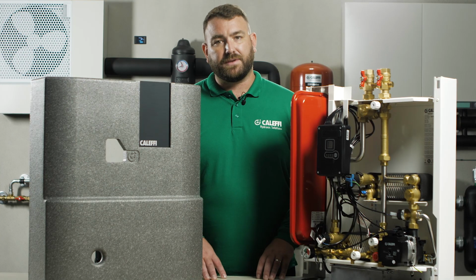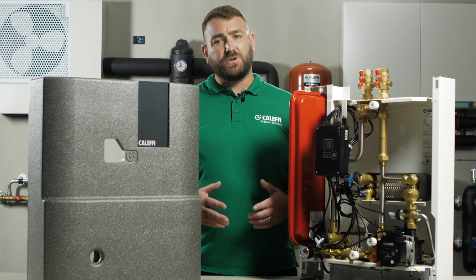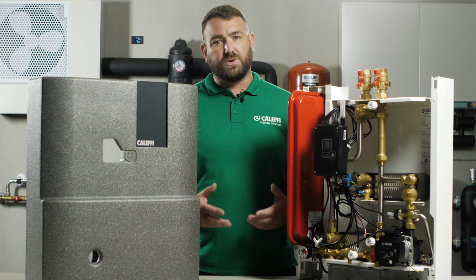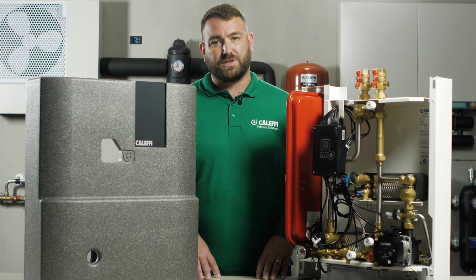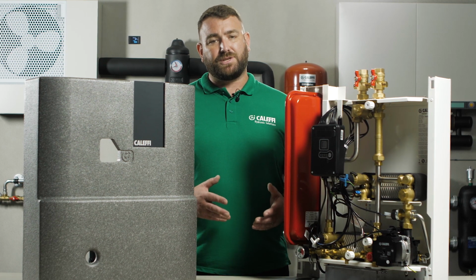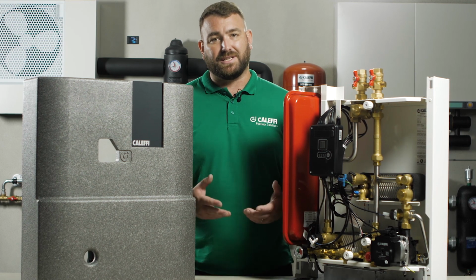The heat or energy is used by the heat interface unit, and the key is to optimise this heat. The hot water coming into the HIU should be used to such a degree that there is a far cooler temperature returning to the heat source. The inlet and outlet temperature differential is called the delta T. The bigger the delta T, the more efficiently energy is used, with benefits to the overall system operation.